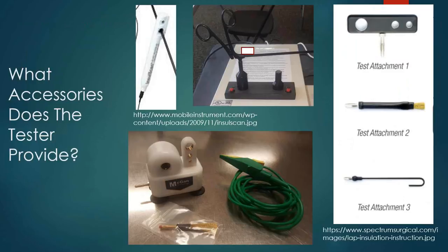So make sure you get educated by the vendor of the tester on what damage looks like with the accessories. Another thing I see, and it's pretty obvious, is that the grounding wire can become damaged a lot quicker than your accessories, because you're using it every time to ground. Understand that you cannot just take color code tape, or tape in general, to wrap around that exposure. That does need to be dealt with, because it could be a safety issue or a fire. So make sure you let your SPD leadership know when the grounding wire becomes damaged, and make sure you remedy that situation.